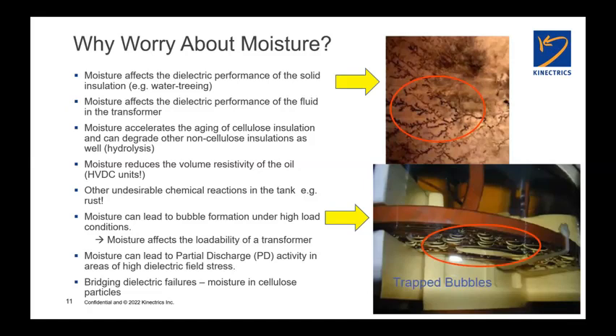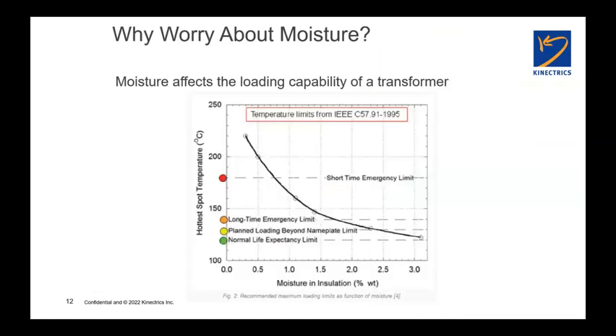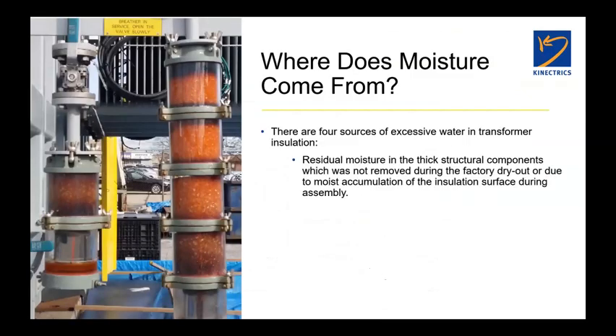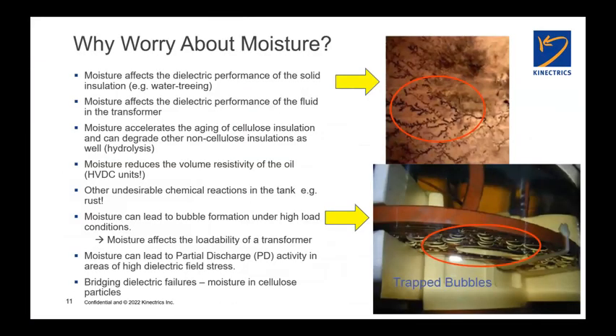Moisture can contribute to partial discharge in areas of high dielectric field stress. Again, the tracking that you see in the top right, the classical treeing structure, that's an indication of that. And then something that I call bridging dielectric failures occur if you have moisture in conjunction with particles floating around in the oil. I'm sorry, I took that slide out. Well, this is one reason why I always tell folks on high voltage units, you want to, from time to time, get what's called a particle count test on your oil.